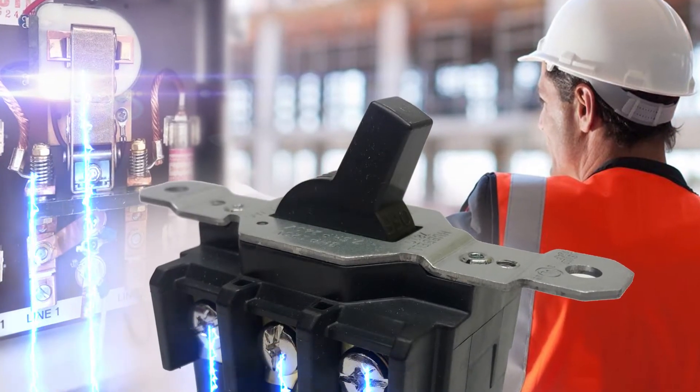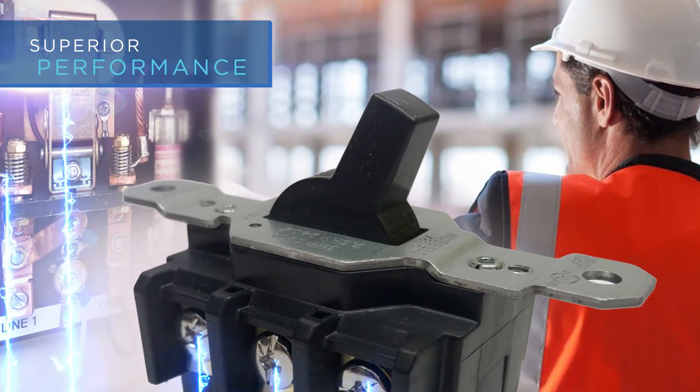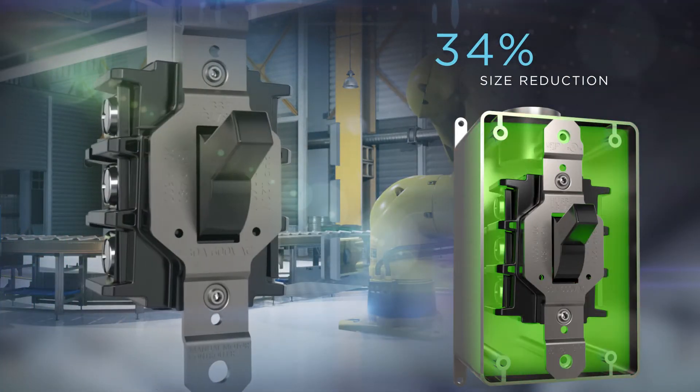Despite being a 30 amp device, the short circuit testing was performed with a 60 amp Class J fuse, making the test significantly more difficult and proving the durability of the switch. The 34% reduction in size now allows electricians the ability to easily install this switch into a standard FD box.